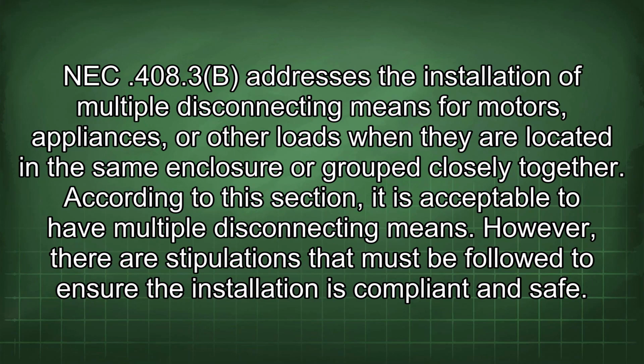NEC 408.3b addresses the installation of multiple disconnecting means for motors, appliances, or other loads when they are located in the same enclosure or grouped closely together. According to this section, it is acceptable to have multiple disconnecting means. However, there are stipulations that must be followed to ensure the installation is compliant and safe.